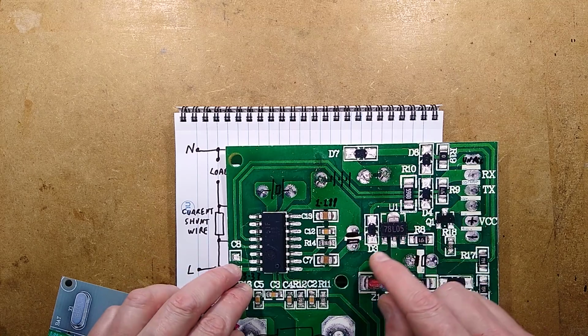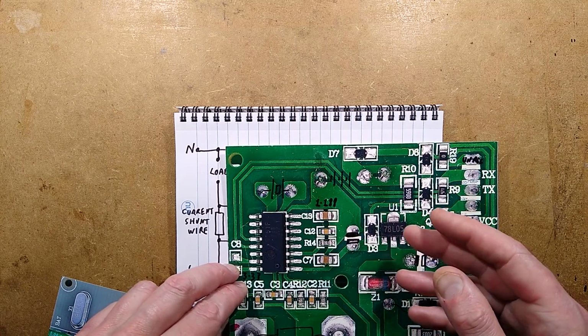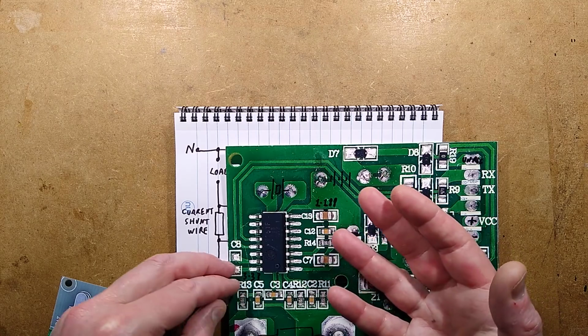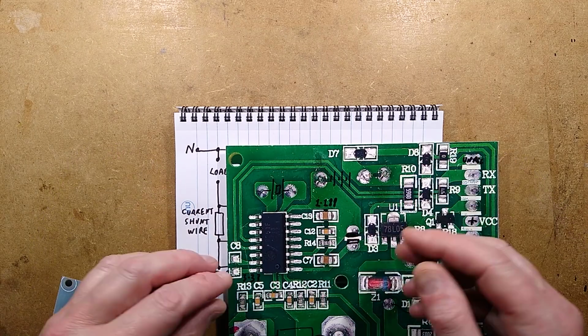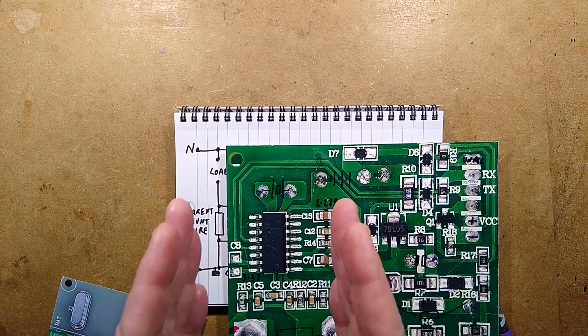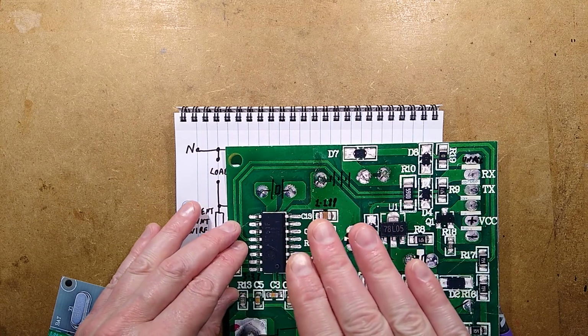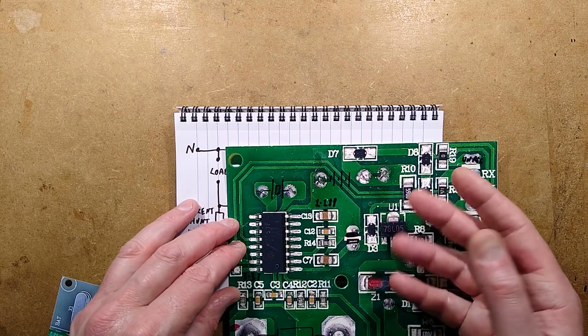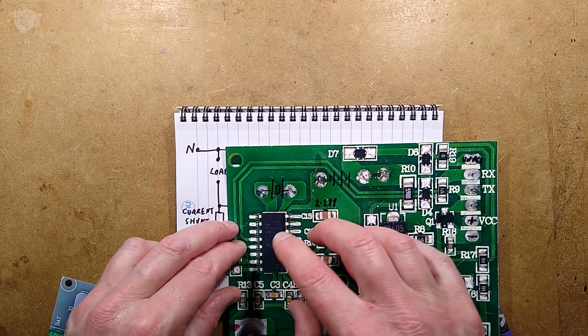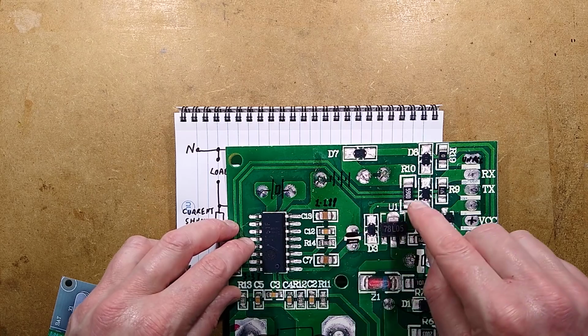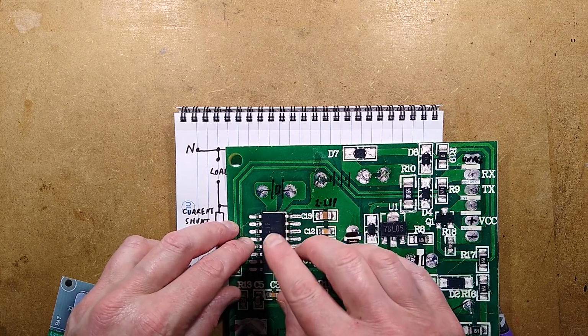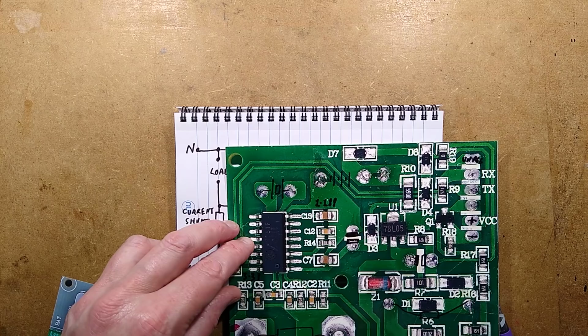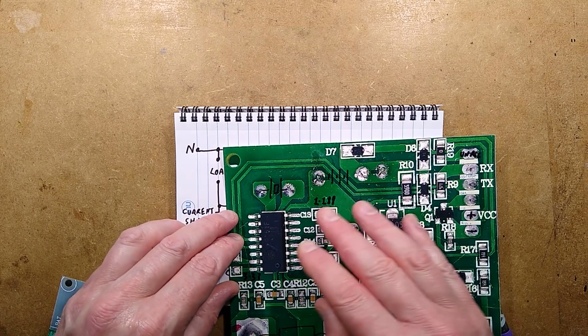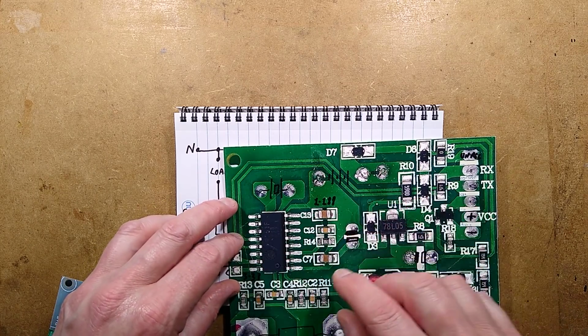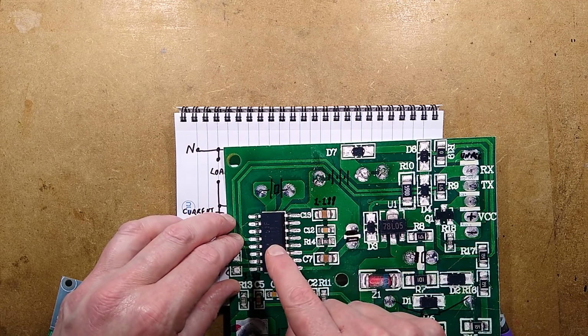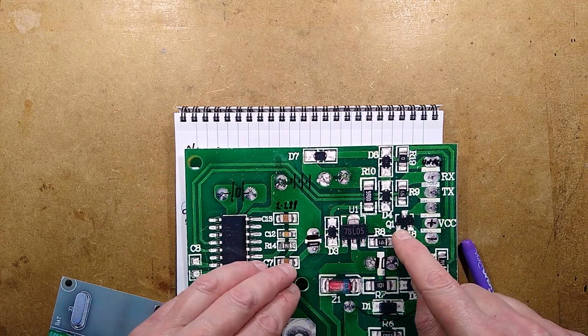the calibration of this unit is done by the microprocessor, perhaps being put into that initialization mode, I'm not really sure, and then a specific voltage being applied to the unit and a specific load of a certain amount of current. And perhaps the processor looks at those, sees what it's getting, knows that they're roughly in the ballpark, and then it will send calibration values and check again, just keep nudging it until it gets its calibration value and then store it in the processor's own memory so that every time it powers up this unit, this chip gets the fresh data. That'll be why it's monitoring for loss of power.